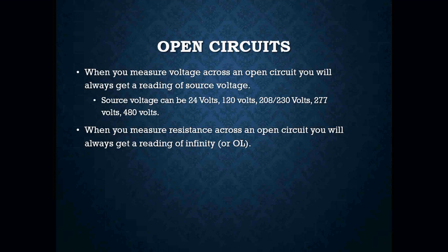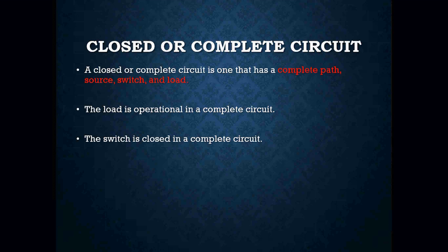When you measure voltage across an open circuit, you will always get a reading of source voltage. Remember, source voltages can be 24 volts, 120 volts, 208, 230, 277, 480, whatever is being supplied to that circuit. It could even be a 9-volt battery on a flashlight. If that circuit is open, you're going to read 9 volts. When you measure resistance across an open circuit, you will always read infinity, or OL, on your meter.